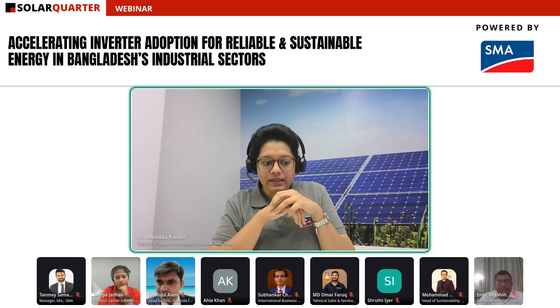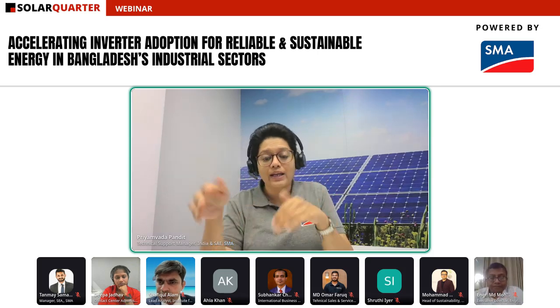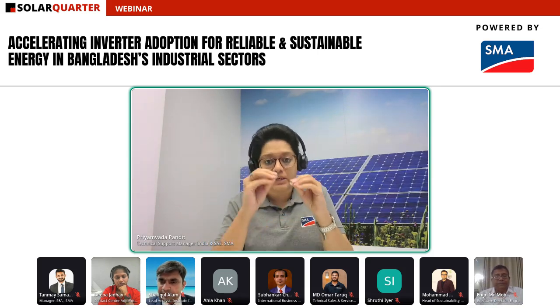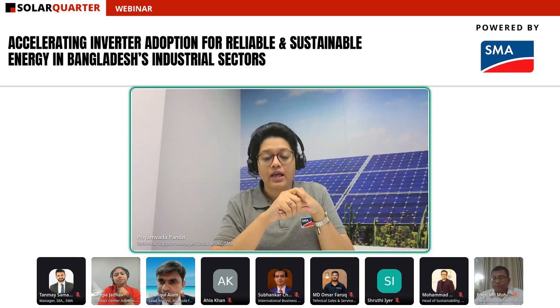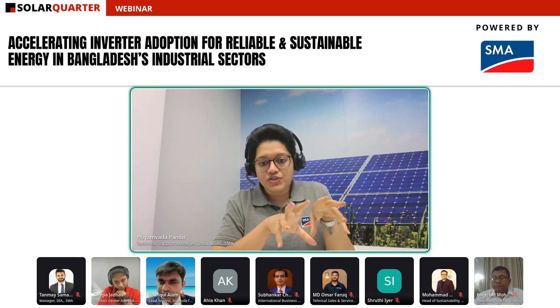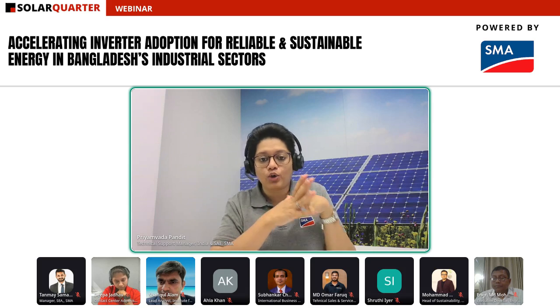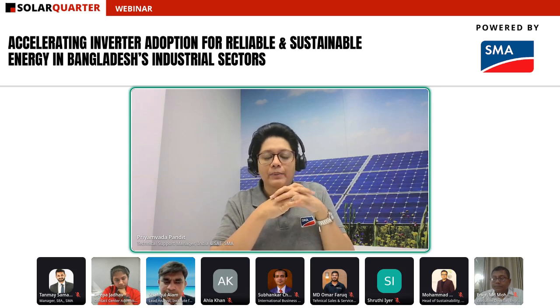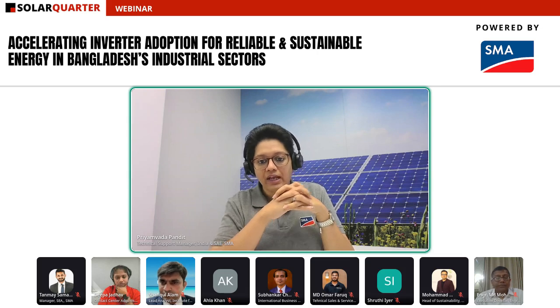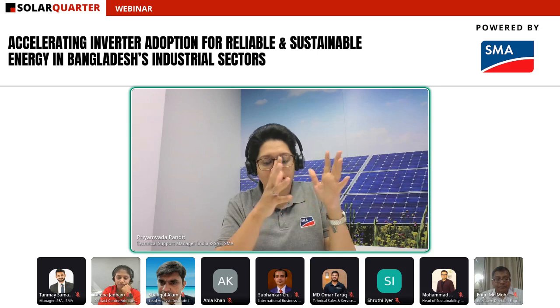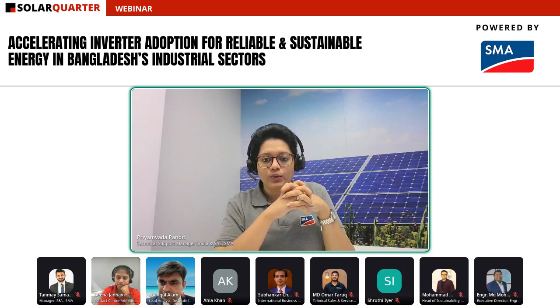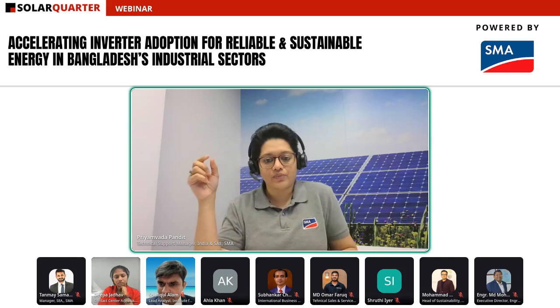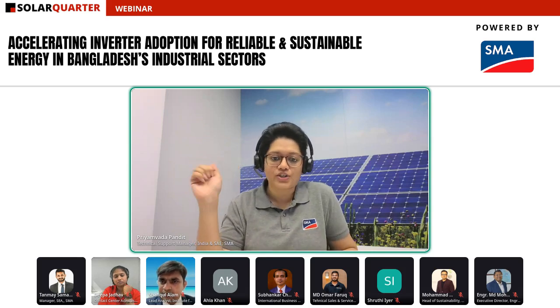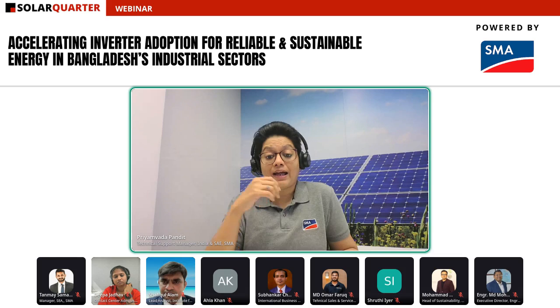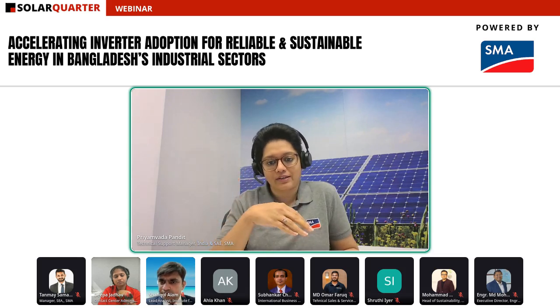But similarly, there are other challenges which you can even solve with this kind of setup. Specifically, very important for the industrial sector is the power factor. Whatever loads you have in the industrial area, they are typically consuming a lot of reactive power. And if you put a solar plant on top of the factory and your systems are operating at, say, unity power factor, suddenly you will see after putting the solar that the power factor at the grid interconnection has gone haywire. It has reduced a lot, and there are penalties if you go beyond a certain value.